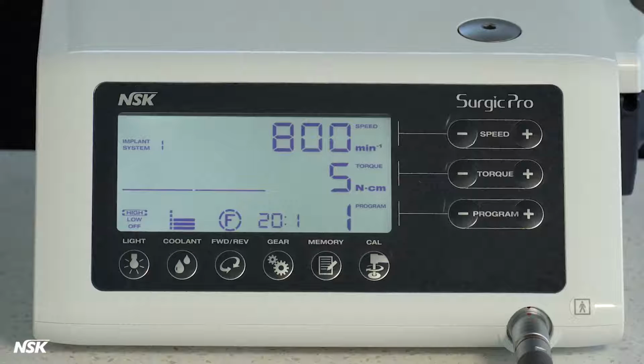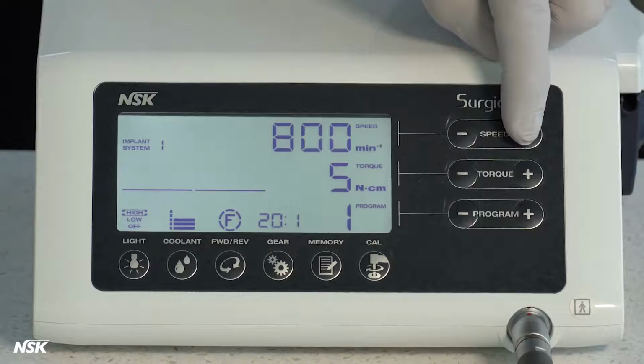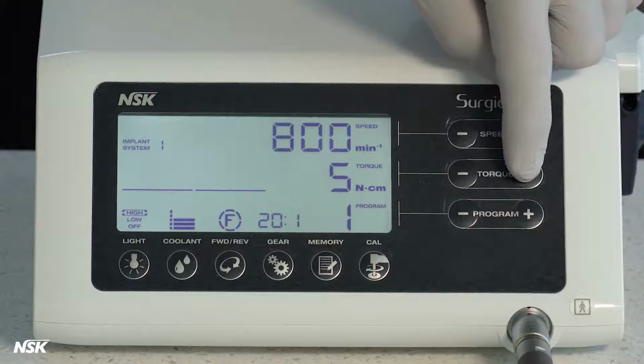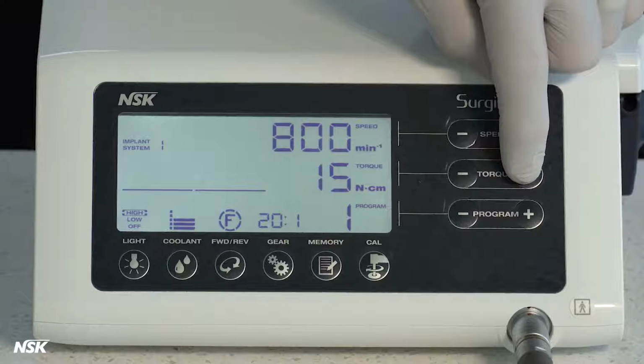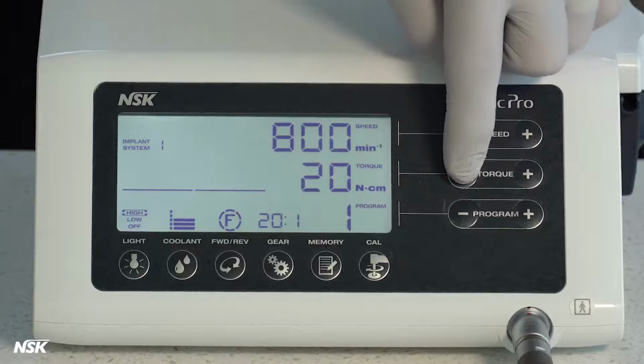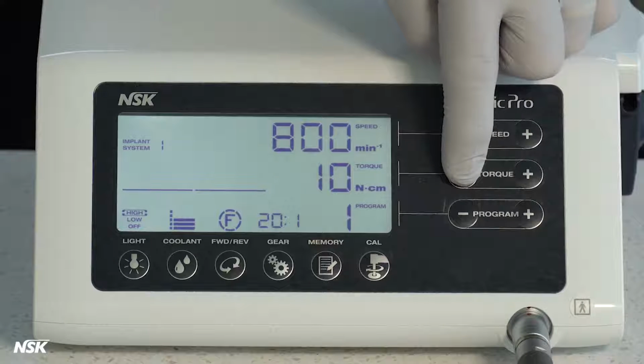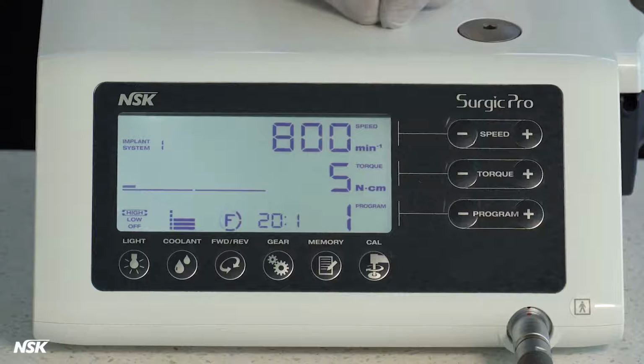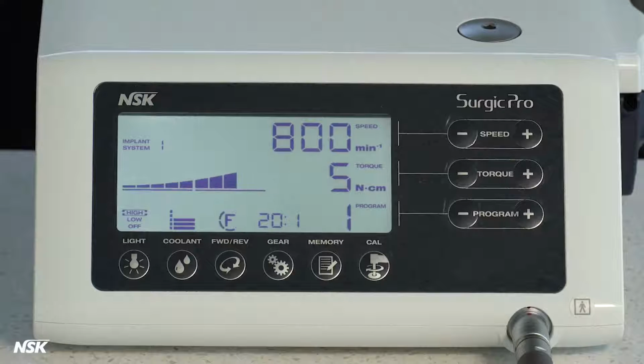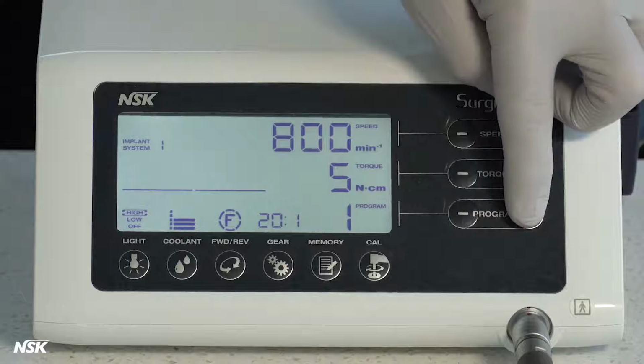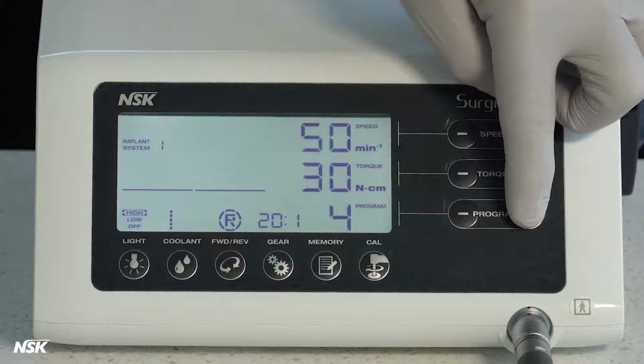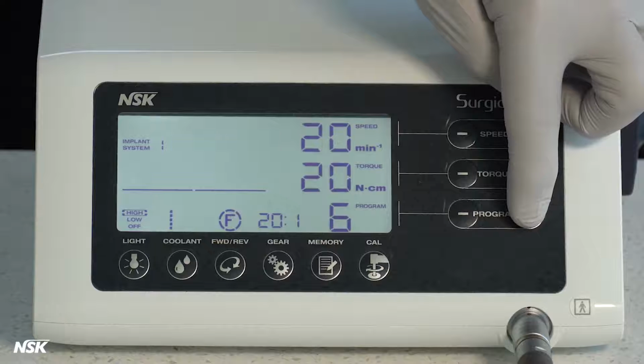Unit controls. Now, let's review the touch panel on the front of the unit and its control buttons. Speed buttons are used to adjust the rotation speed. Torque buttons are used to change or set the torque values between 5 and 80 Newton-centimeters for implant attachments. You will notice the amount of bone resistance applied to the drill is displayed here like a graph during operation. Program buttons will select any of 8 programs in each of 8 implant systems.